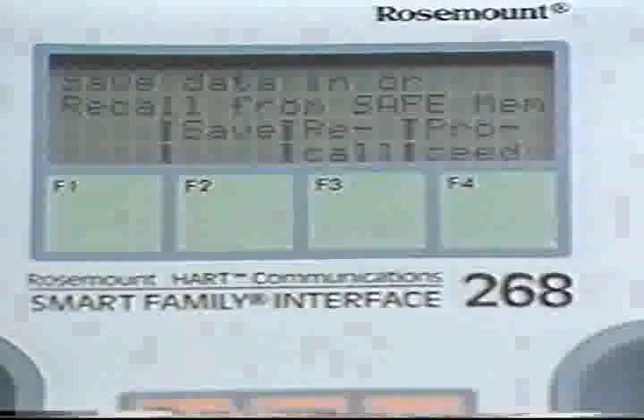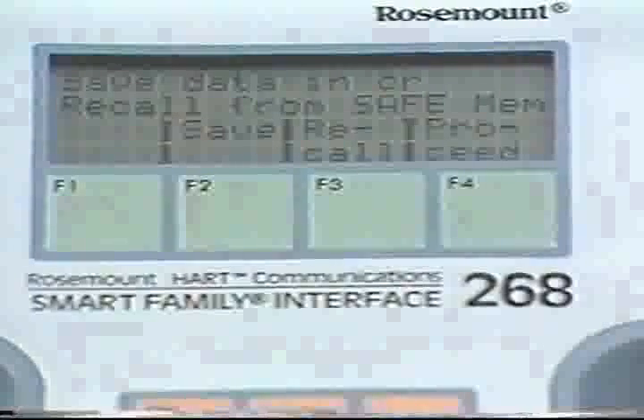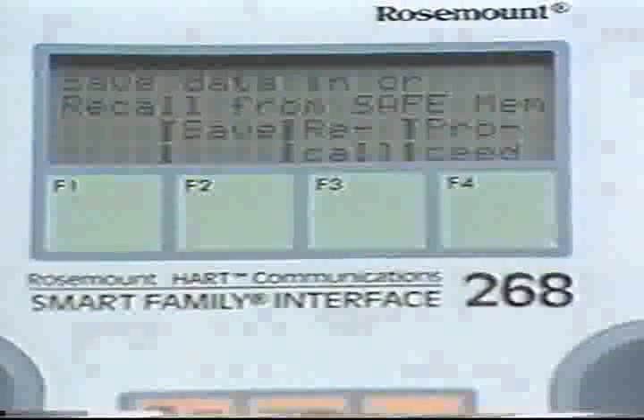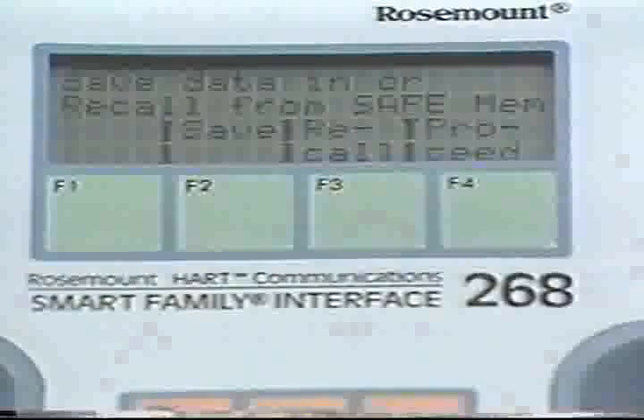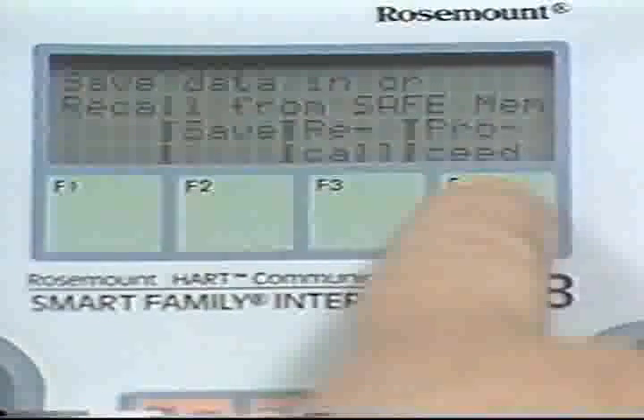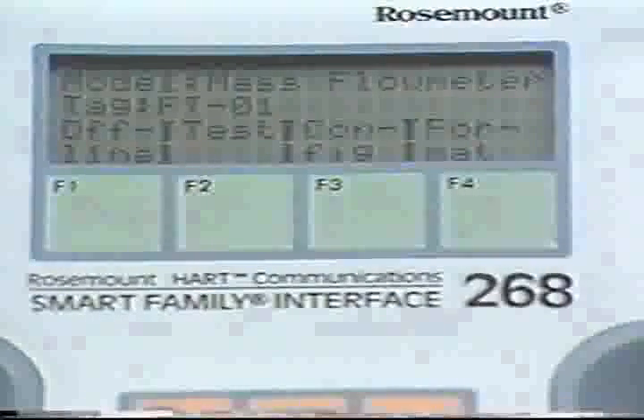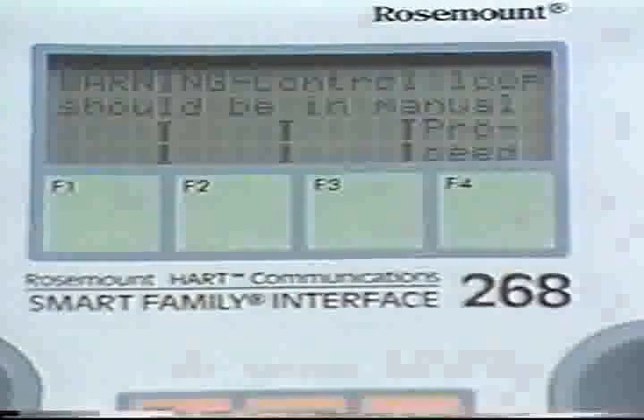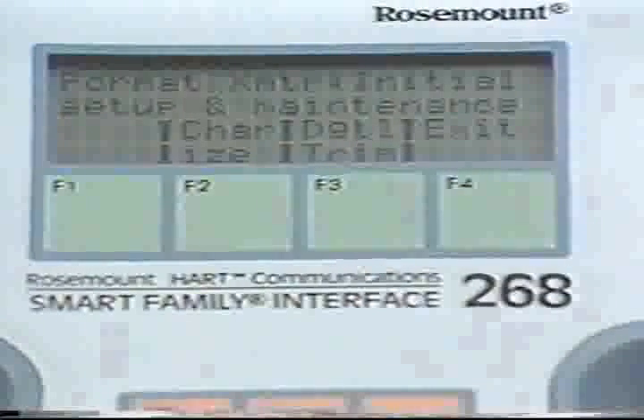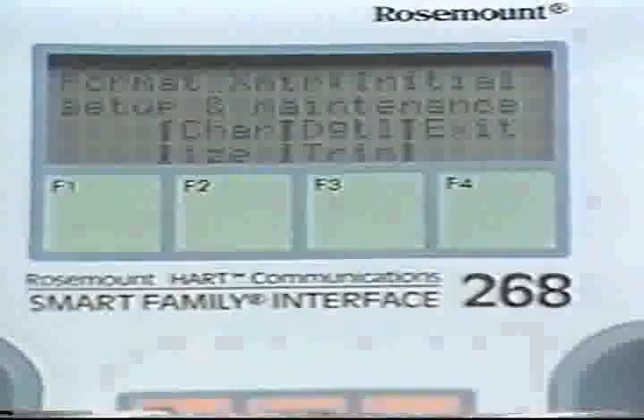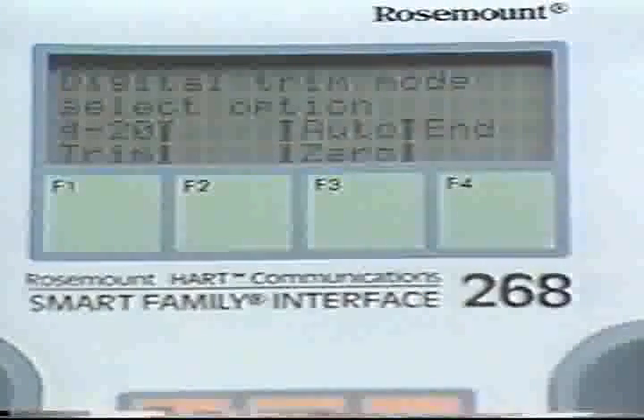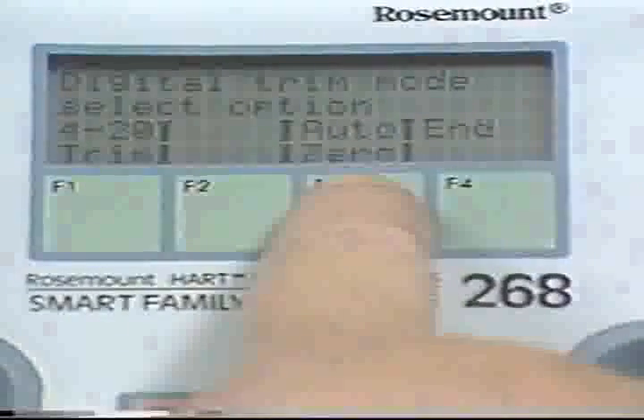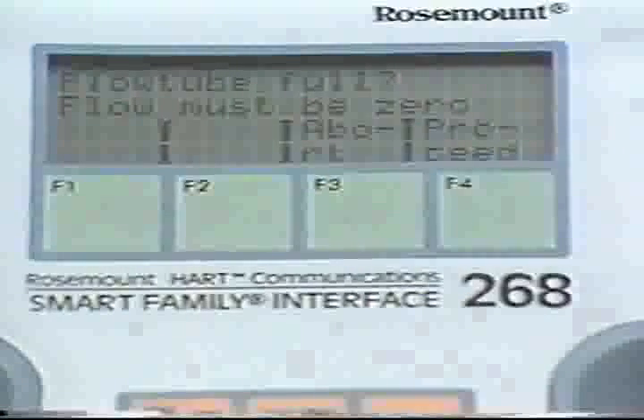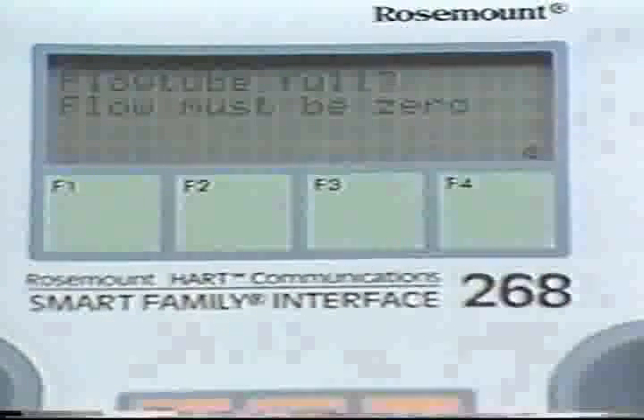To establish the zero and span values, the flow tube must be full of process liquid with no flow. Because actual process fluid is used, this procedure is typically done on an installed transmitter. To begin, Format is pressed, followed by the Proceed key. To establish zero, simply press the Auto Zero key. The Auto Zero automatically establishes zero to the properties of the process fluid. The resulting display will indicate that the mass flow meter is properly calibrated.